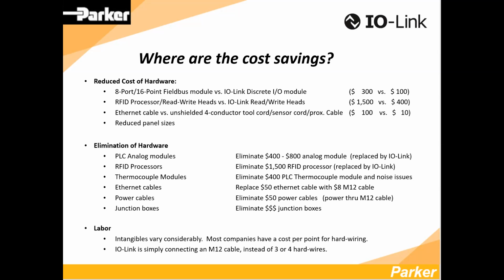Reduced panels, even junction boxes, can be eliminated. You're saving because you're getting stuff out of panels and boxes, so you can reduce their size. With analog applications, you'd normally have shielded cables out to your analog sensor, inducing noise issues you have to deal with, plus routing cables all the way to an analog module in the PLC. That module can go away, because now you're buying an IO-Link version instead.